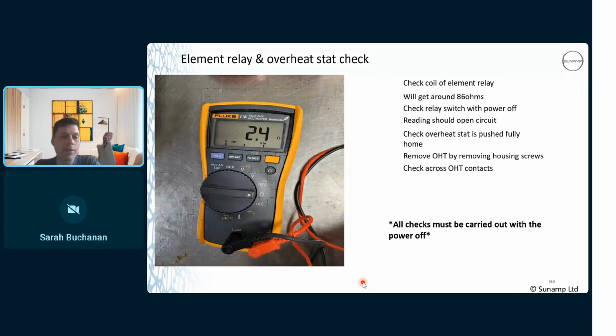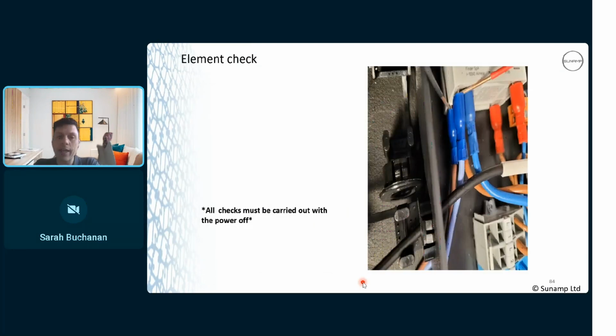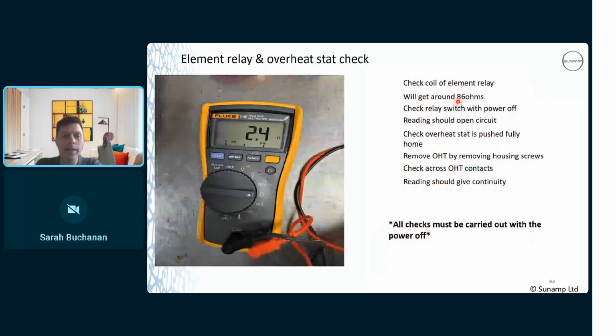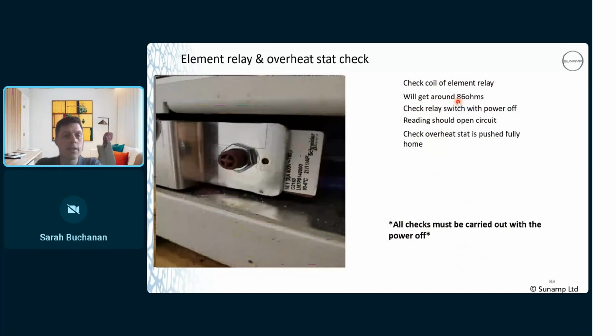So even if you're getting a high resistance, you may have had an intermittent fault and it's tripping the overheat stat. If you get a form of resistance going through there, it might not work properly. It should be giving continuity. You can check the element as well, the element circuit. So that's if you can get your probes into the contacts of the relay, the output terminals of the relay. So if we go back a few slides, where are we? So the output terminals in this here would be these two relay terminals here.